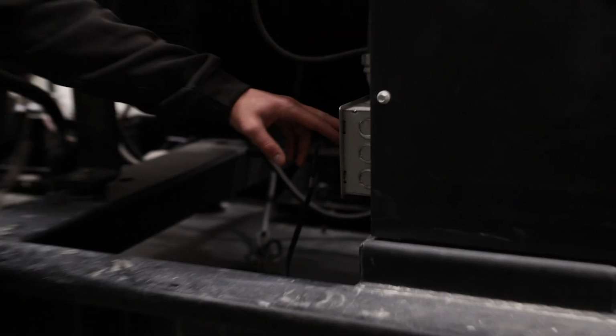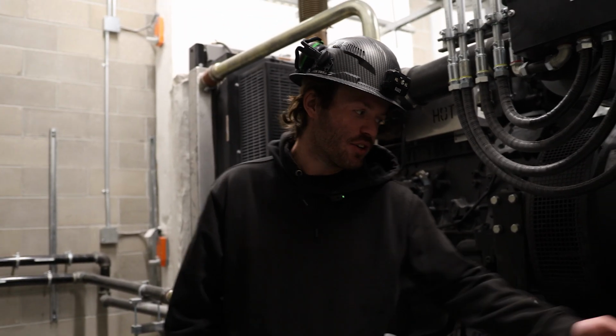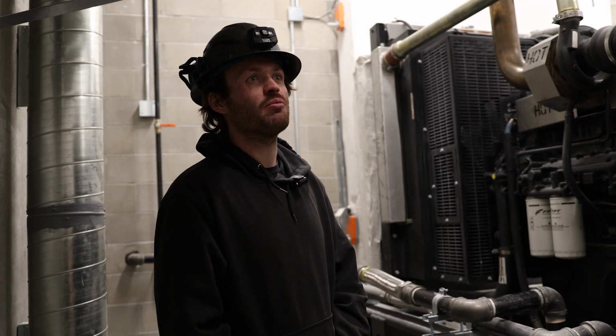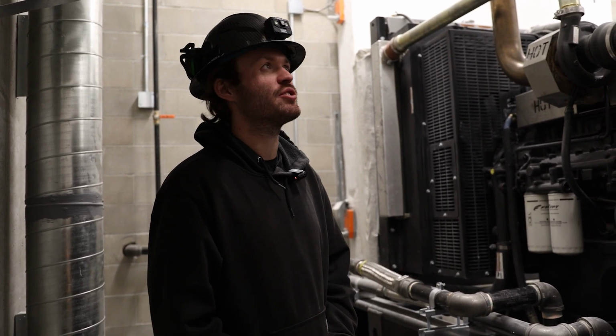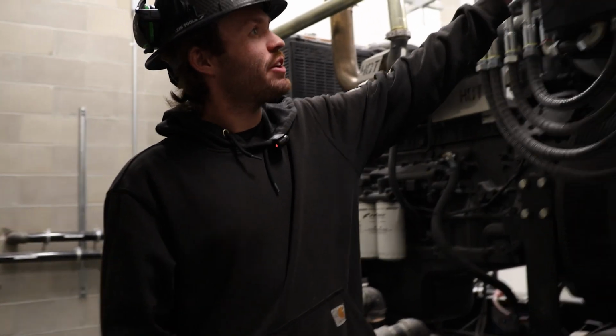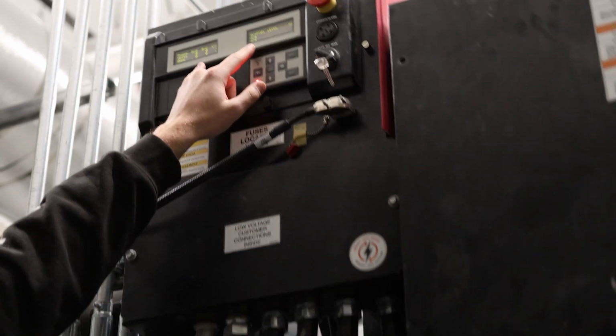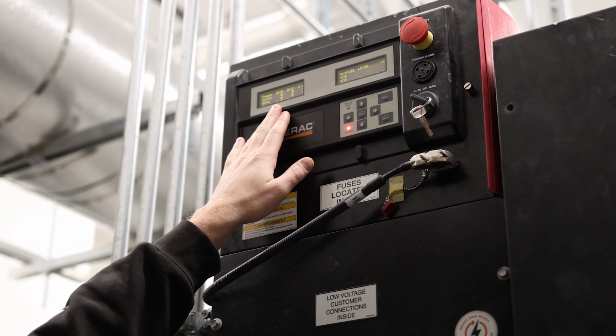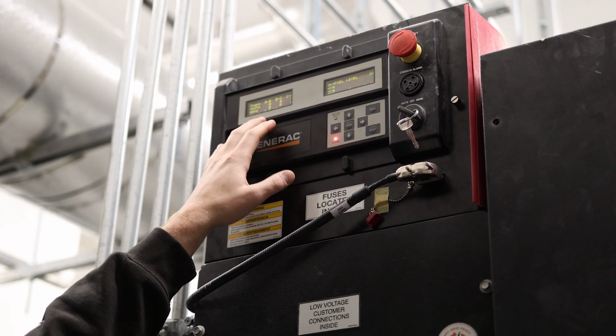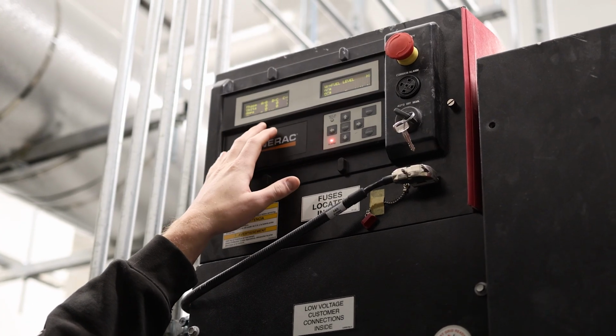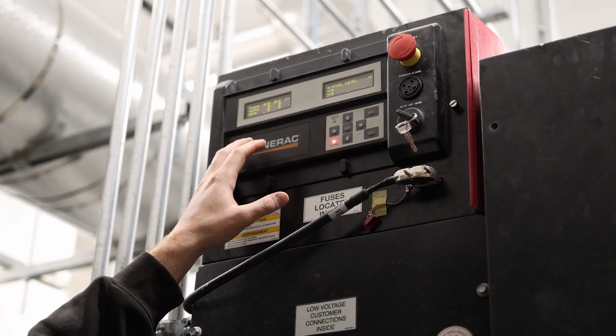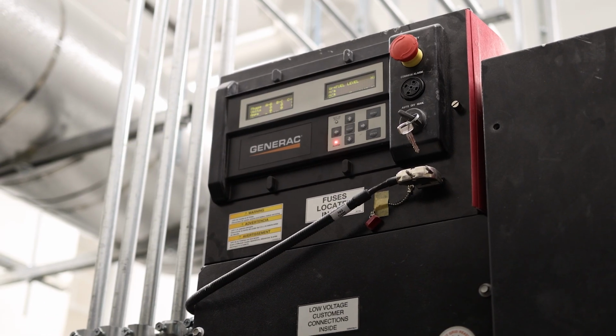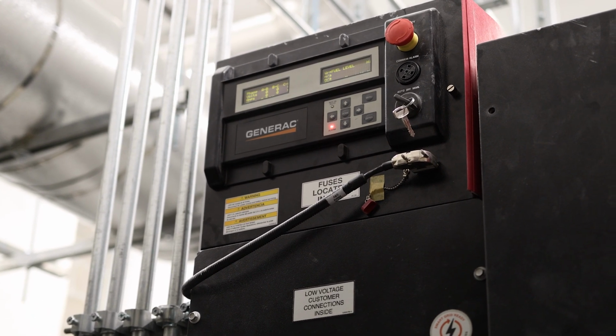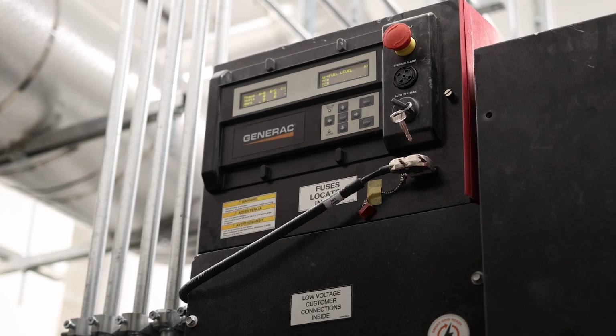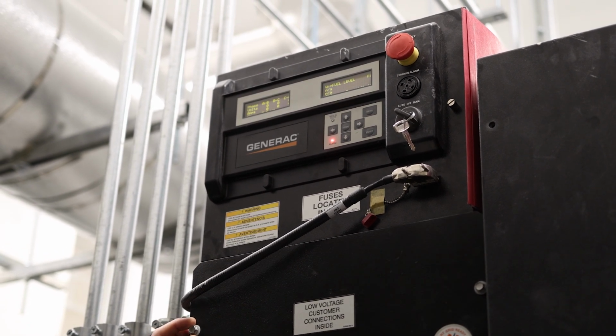2 outlets here, a 240 volt one, which is dedicated for our coolant heater, as well as a 110 volt one. The 110 volt one is generally just there if you're working on the unit, need to plug in a light, plug in a battery charger, something of that nature. Moving on, we'll go to the controller of the generator. 2 screens, both can be changed. The left screen generally is kept on the volt and amp page. This will show us our generator's output: volts, amps, kilowatts, and frequency. It's the most common page to keep there to monitor what the generator is doing and how it's outputting voltage, and it's needed when you record your readings for inspections, testing, of that nature.